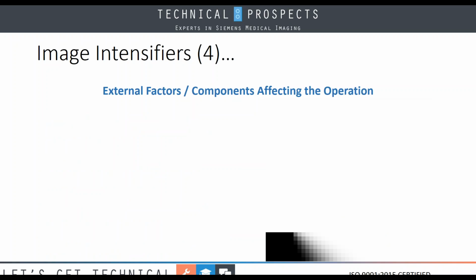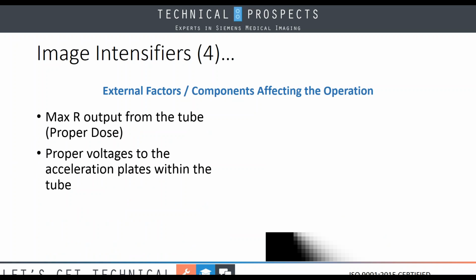Some factors that we can look at, and components that affect the operation externally, the biggest one is the max R output from the tube. This is ensuring the proper dose. This is something that you as field engineers need to ensure that we have the proper dose coming into the image intensifier. The second thing that is very important to the image intensifier is the proper voltage to the acceleration plates that are within the tube. Now, you need to be highly careful here because this is very high voltage. The image intensifier will typically have upwards of 30,000 volts on that last acceleration plate. What a lot of manufacturers do is they build in a voltage divider for you to test the different voltages on the side of the modern day image intensifier. This is something you should be looking at every PM to ensure good image quality.